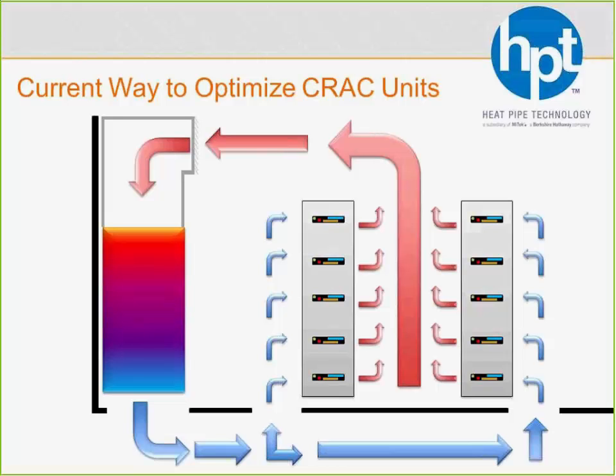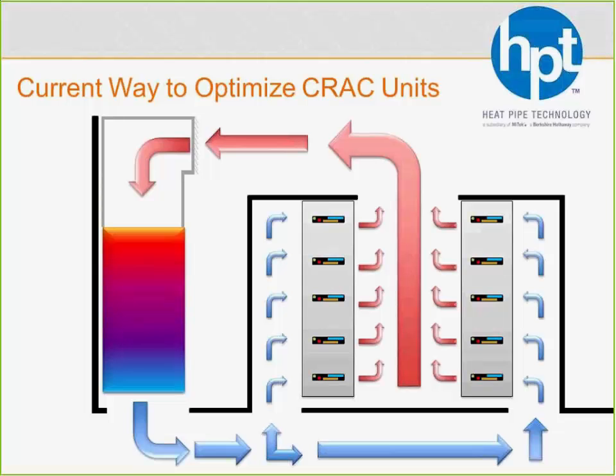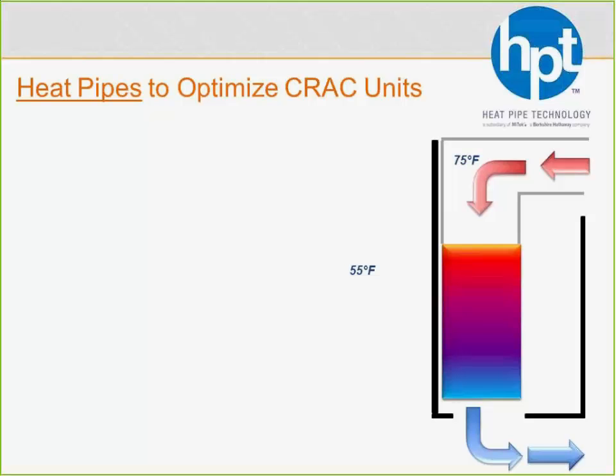So how do you optimize this system? Well, the way they're currently doing it is simply encasing those stacks to reduce the amount of airflow that's needed, and then actually ducting that return. That's one way to optimize the system. Of course, another way is to use some heat recovery to reduce the amount of load on those CRAC units. And of course, a great way to do that is with, you guessed it, a heat pipe.